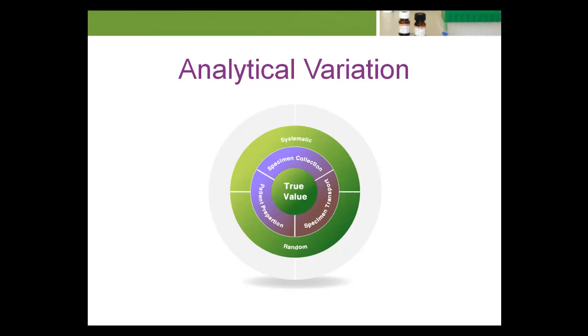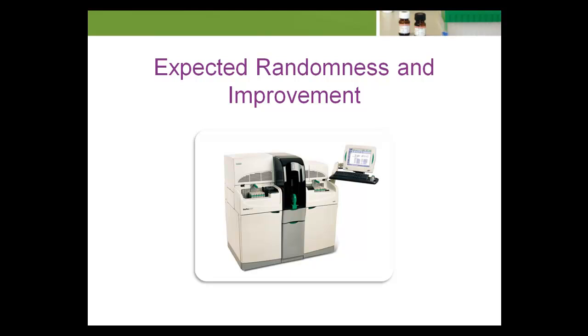Let's look more closely at each form and what contributes to their causes. Random variation is also known as imprecision. Random variation is the measurement of ongoing randomness in a test system. Each instrument or kit has a certain amount of expected randomness, as described by the manufacturer in the manual or product insert. As instruments become more computerized and methods become more stable and specific, imprecision has slowly improved.